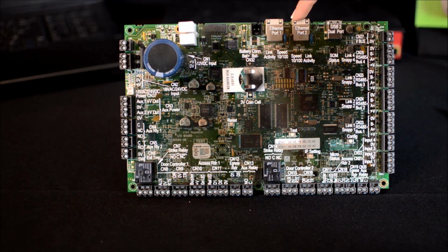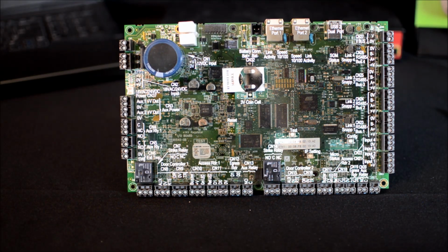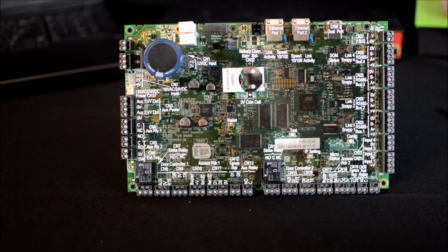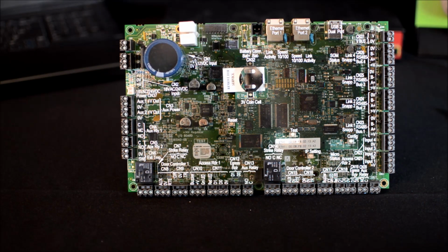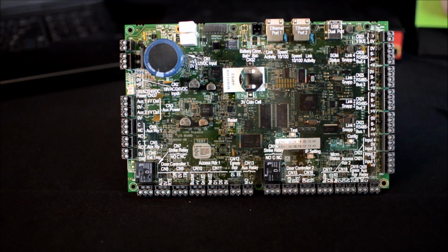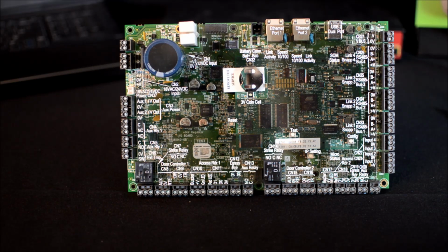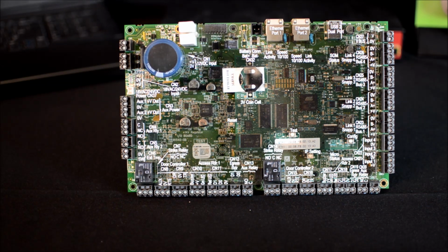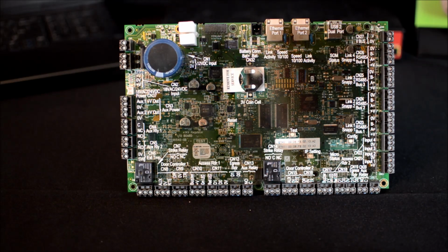To the left of the USB ports, you will see the Ethernet port 2. It has been configured with a static IP address from the factory and is utilized upon initial setup of the panel's parameters. Once a non-factory IP address is assigned to the panel, Ethernet port 1 is used. Ethernet port 1 is located to the left of Ethernet port 2 and is designed to be used for the day-to-day LAN or WAN network communications of your system.